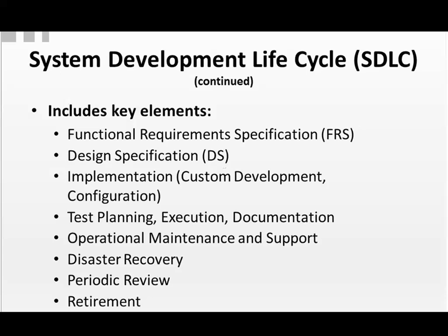Now, with your SDLC, you would start with your validation plan, and that plan would address all of these key elements. You have your functional requirements specification to say what the system is expected to do. Design specification, how that functionality is delivered. The functional requirements are the what, the design is the how. And you also want to make sure that every functional requirement is unique and testable. You also will have other requirements, system performance requirements, maybe security requirements, other types of requirements that relate to the use of the system.